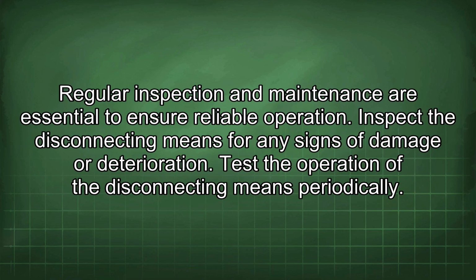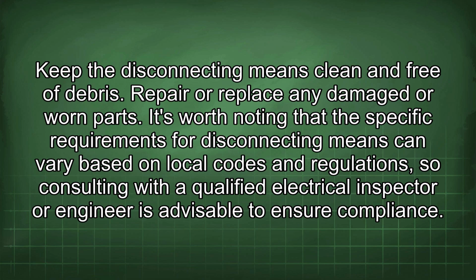Regular inspection and maintenance are essential to ensure reliable operation. Inspect the disconnecting means for any signs of damage or deterioration. Test the operation of the disconnecting means periodically. Keep the disconnecting means clean and free of debris. Repair or replace any damaged or worn parts. It's worth noting that the specific requirements for disconnecting means can vary based on local codes and regulations, so consulting with a qualified electrical inspector or engineer is advisable to ensure compliance.